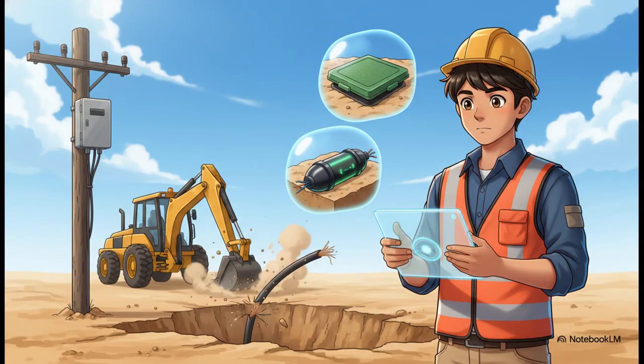Now, what happens if a backhoe tears up an underground cable and you need to splice it? Well, Rule 12-112 gives you 3 perfectly legal ways to do this if the original run is damaged. 1, you can bring it up to a junction box protected from mechanical damage at least 1 meter above grade. 2, you can use an approved splicing kit meant for direct earth burial. Or 3, you can use a grade-level in-ground enclosure with splice connectors suitable for wet locations. Ultimately, accessibility and moisture protection are the core safety reasons behind every single one of these options.